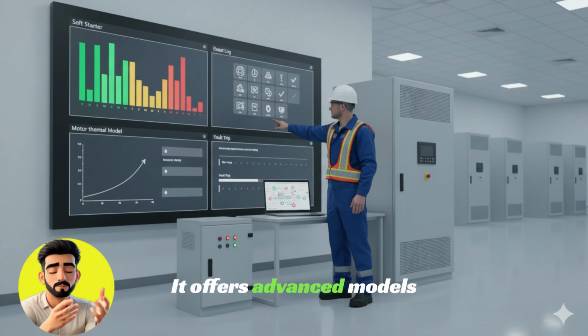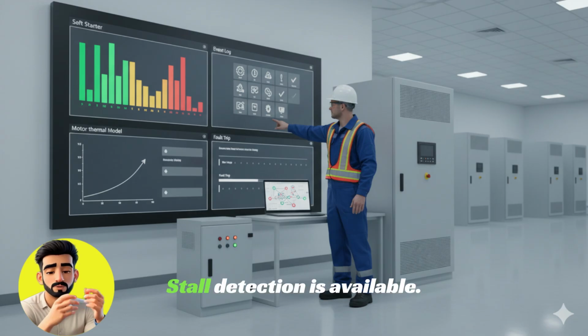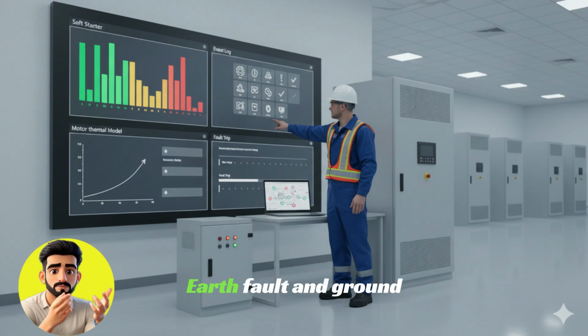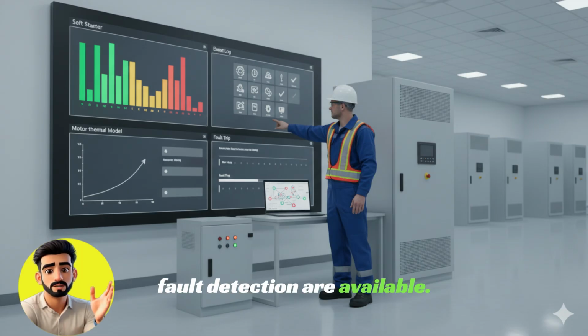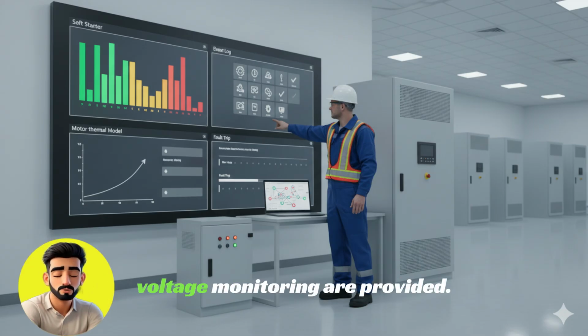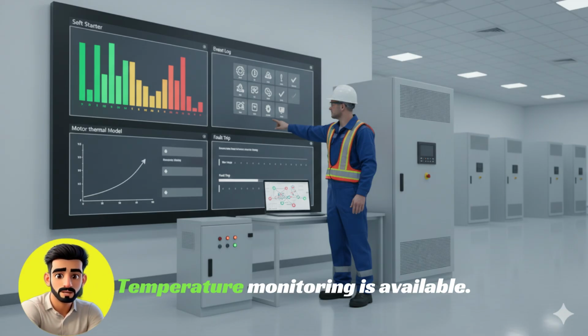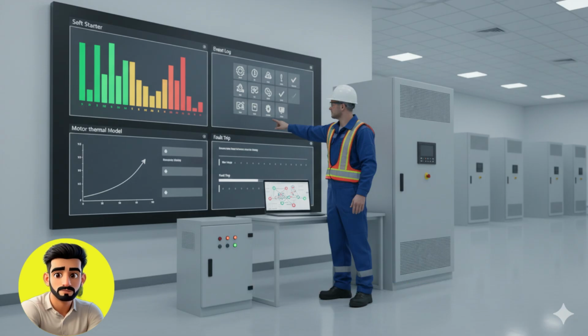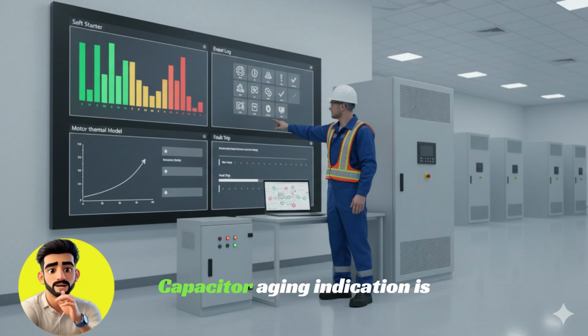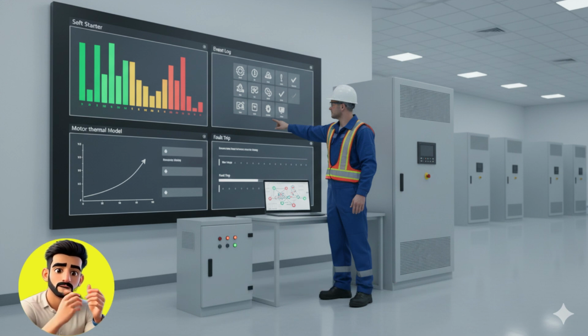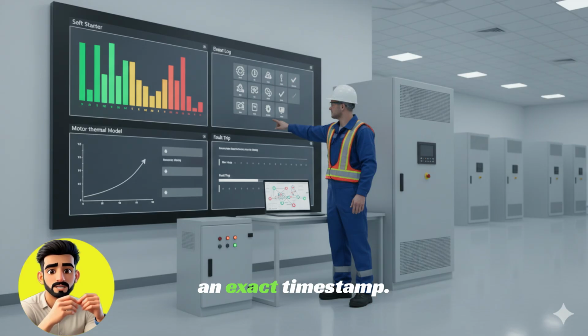It offers advanced models for motor overload. Stall detection is available. Earth fault and ground fault detection are available. Over voltage and under voltage monitoring are provided. Temperature monitoring is available. Fan life alarm is given. Capacitor aging indication is provided. Trip history is available. And each fault has an exact timestamp.